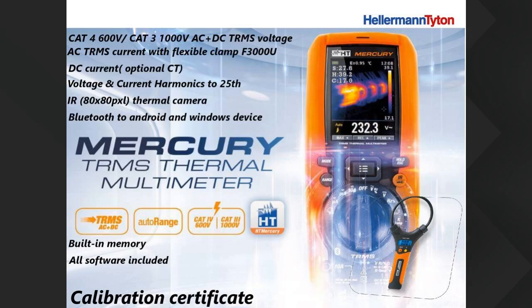Then this meter can also measure the voltage and current harmonics up to the 25th. And then the nice feature of this meter is that it's got a thermal camera. It's an IR 80 by 80 pixel thermal camera built in. And what's nice about that is that it allows you to connect to your cell phone or tablet via Bluetooth. And the software is a free software download called HT Mercury. Also in the package, there's software that you can load onto your Windows computer. So it's got a built-in memory, but you can add a small SD card internally as well.